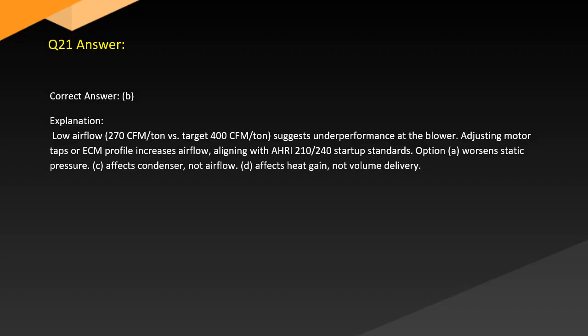Answer. Correct answer, B. Explanation. Low airflow, 270 CFM per ton versus target 400 CFM per ton, suggests underperformance at the blower. Adjusting motor taps or ECM profile increases airflow, aligning with AHRI 210/240 startup standards. Option A worsens static pressure. C. Affects condenser, not airflow. D. Affects heat gain, not volume delivery.